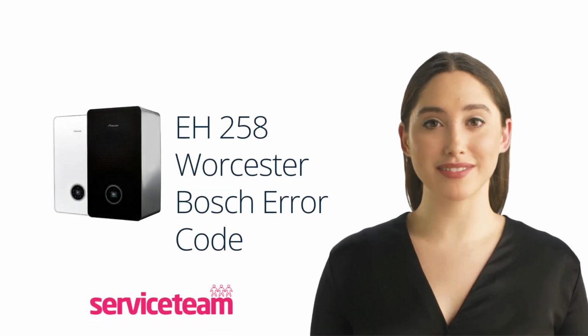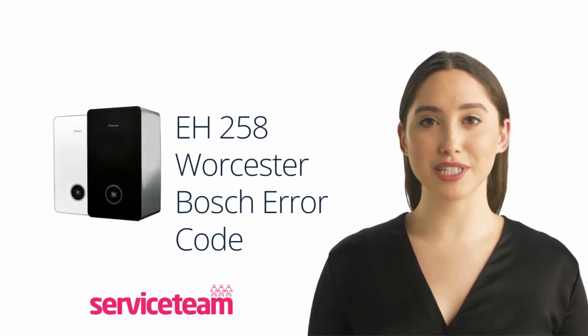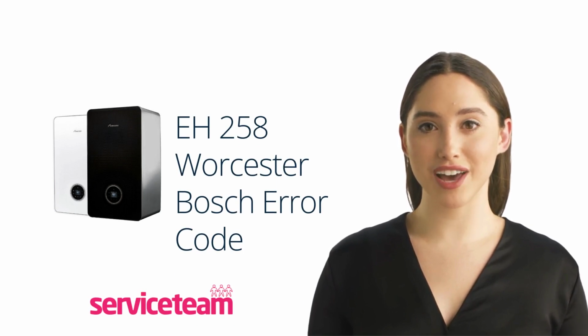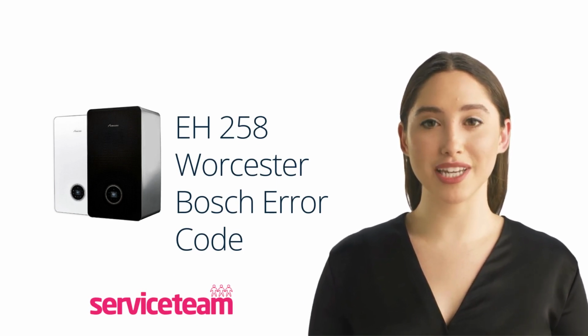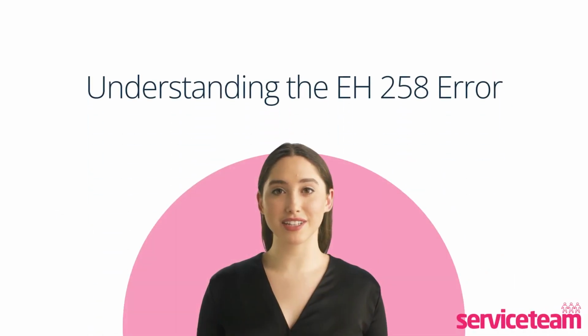Boiler error codes, like EH258, can be crucial for your safety. Let's understand and fix the EH258 error code on your Worcester Bosch boiler.